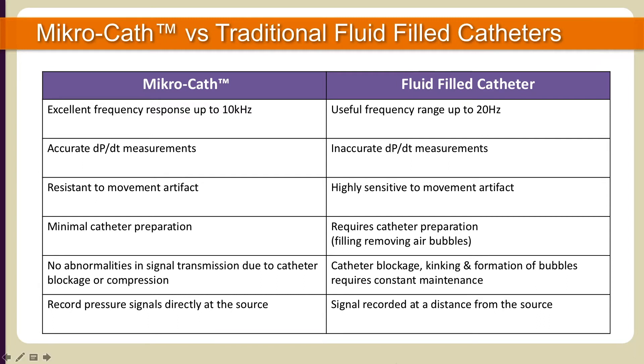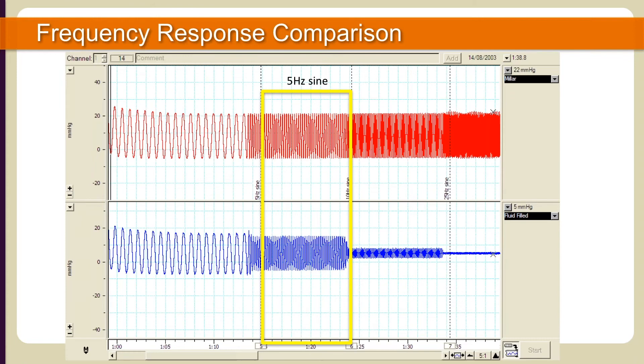This table draws a comparison between the Mikro-Cath and traditional fluid-filled catheters. The Mikro-Cath's high-frequency response provides greater accuracy than traditional fluid-filled catheters and makes it possible to measure dP/dt with higher reliability. The Mikro-Cath sensor is positioned at the pressure source, whereas the transducer used in fluid-filled catheters is positioned externally from the patient. This LabChart tracing provides a comparison: the red channel represents Millar's high-fidelity signal, and the blue channel is the signal acquired from a fluid-filled catheter. Note the signal attenuation on the fluid-filled blue channel when the frequency of the pulse waveform increases from 5 Hz to 10 Hz.